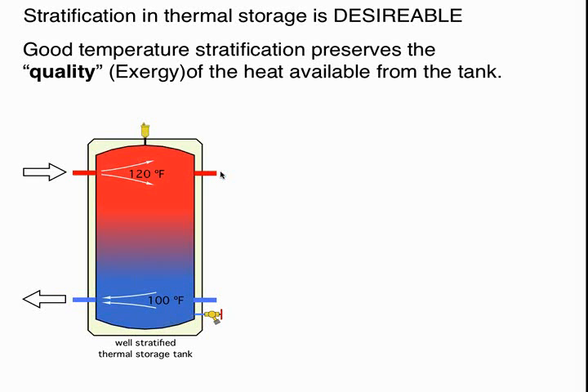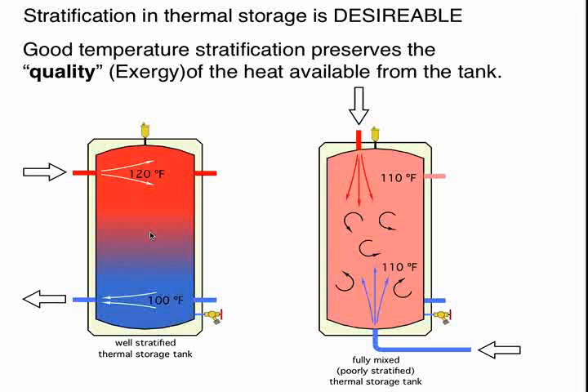And just to illustrate that, here we have a tank that is stratified. We have 120-degree water in the upper portion of the tank. We have 100-degree water in the lower portion of the tank. Let's assume that we had a linear gradient from top to bottom in the tank. So our average tank temperature here would be about 110 degrees Fahrenheit. Now, if I were to stir that tank up without adding any energy to it, I'd have this picture over here. And I can show you a couple ways to stir up a tank.